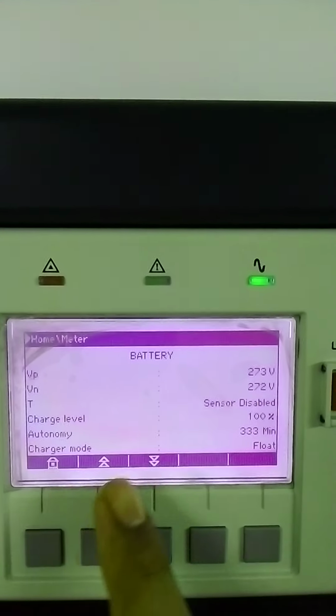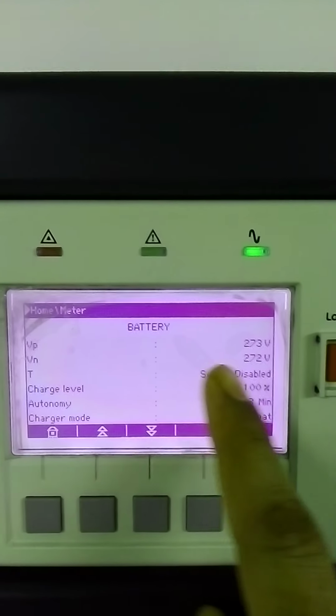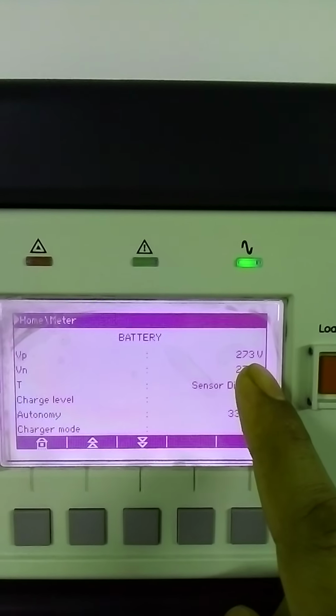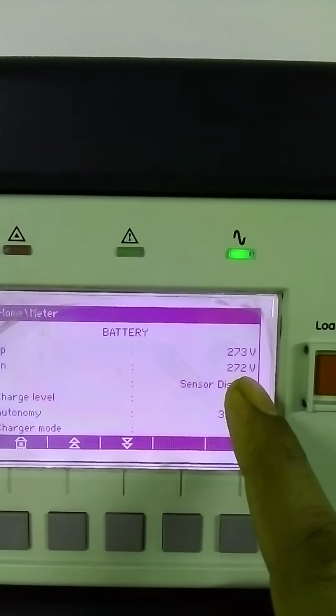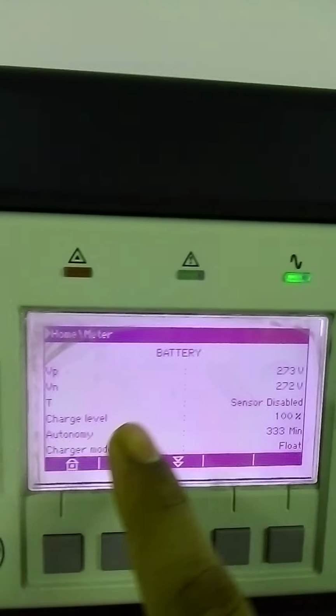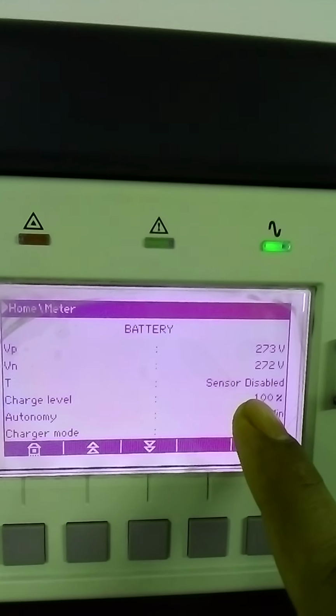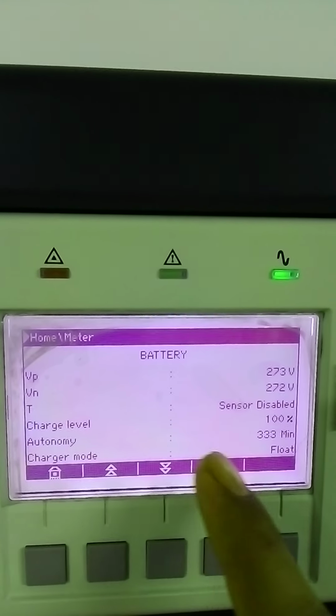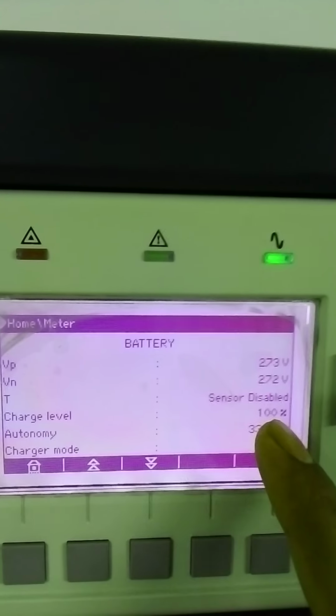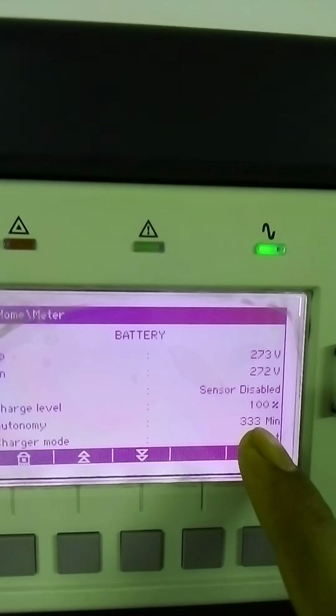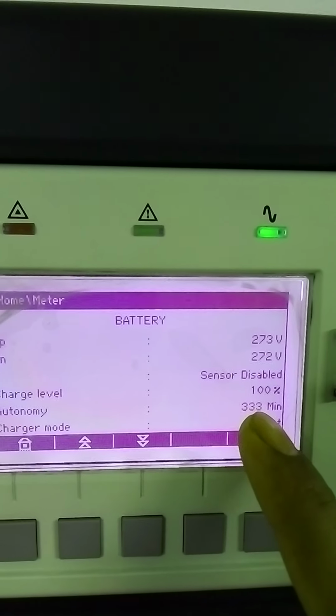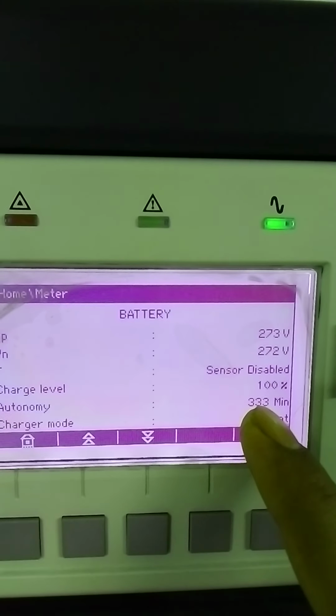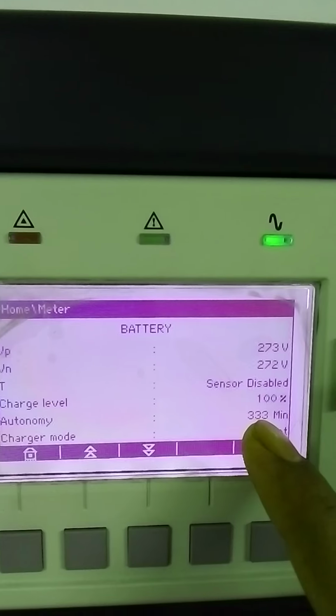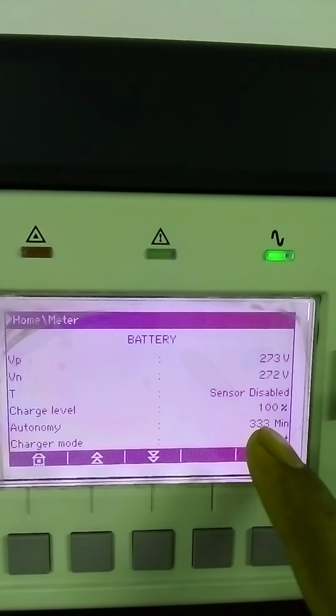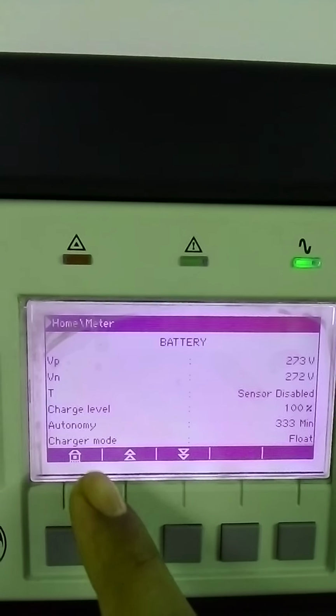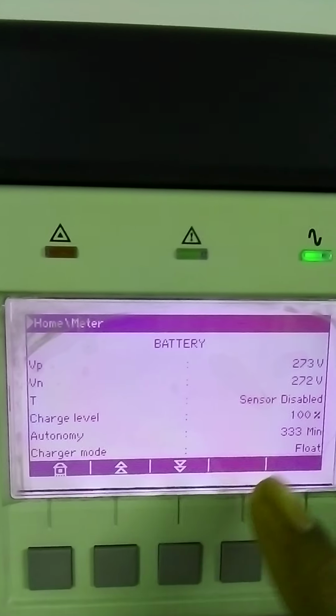meter. You can see here it's showing the battery. This is the voltage, 273 volt from the battery, 272 volt. You can see this is the temperature sensor T. Currently it is disabled. You can see the charge level of the battery is 100%. If the main power goes off, you can run your UPS for 333 minutes. This is the backup duration of your batteries, and you can see the charger mode is float.